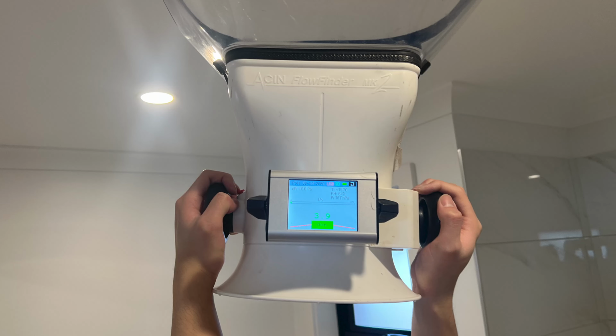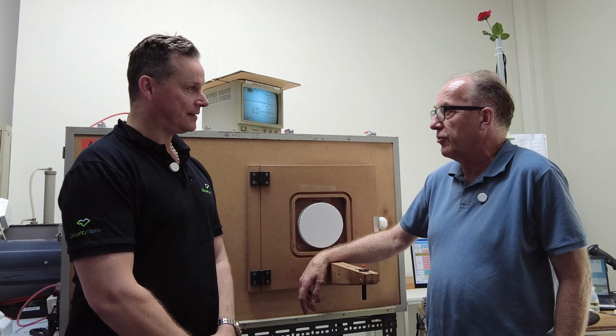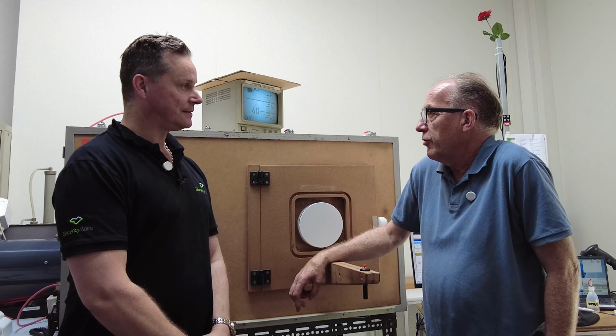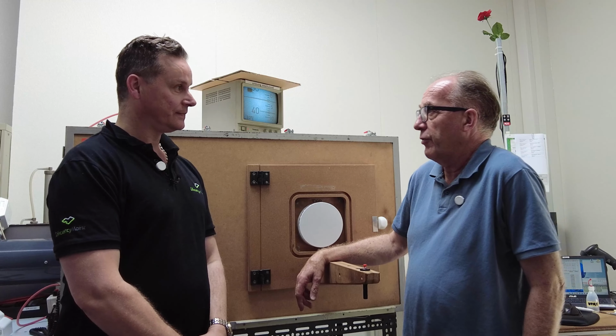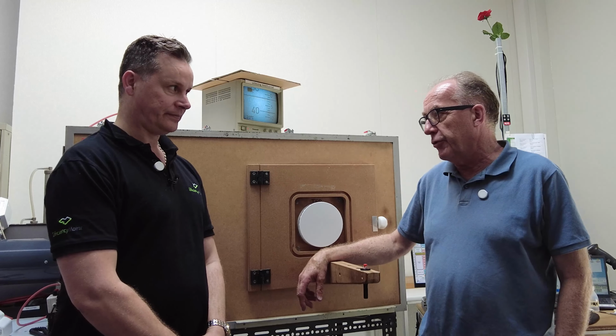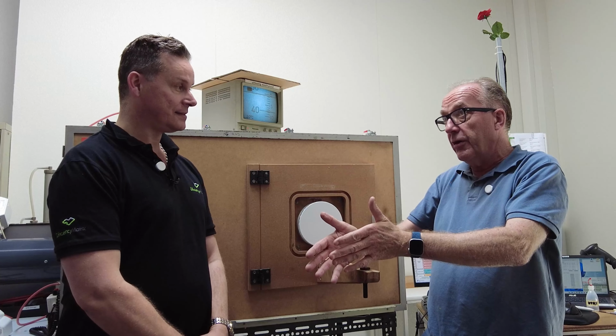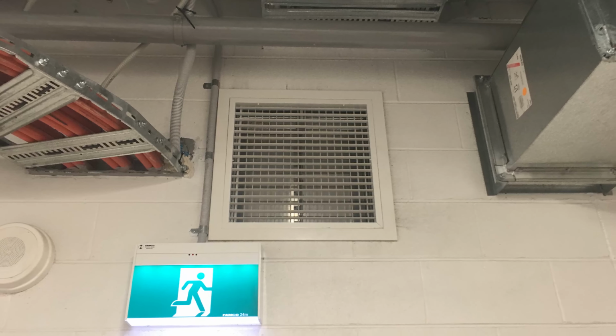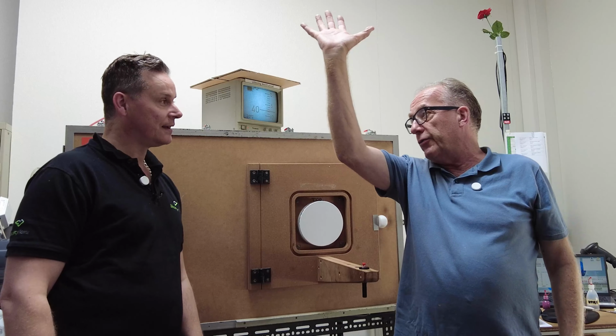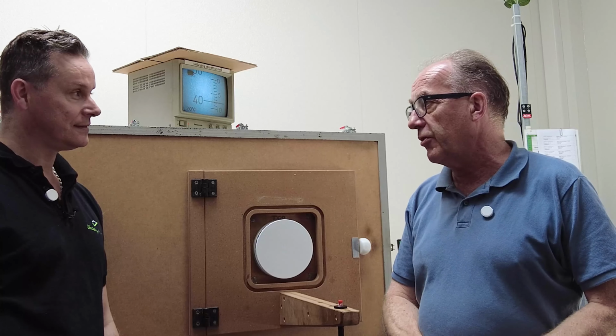In fact, when you put a flow hood on a ventilation system, you are extending the ventilation system with an extra duct, so to say. And ducts do have resistance. If you have a duct which goes from a large size to a small size, this is the grill, here is the flow, and you can imagine it is as if you are putting your hand on the duct and the flow is going somewhere else, putting a resistance in the system.